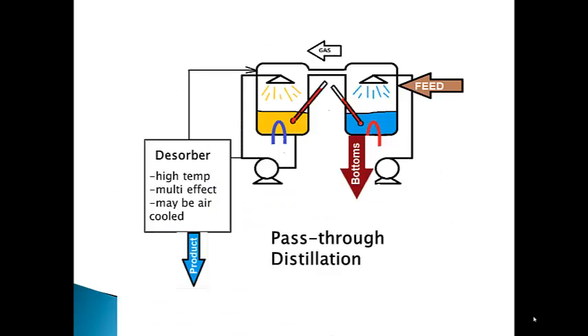We have learned that the desorber may operate with a very high temperature first effect, that it can have up to 4 effects, and that it may be air-cooled. But to operate at all, it needs a vacuum pump. An absorption chiller does not have one because it is a closed system. But pass-through distillation is an open system. Dissolved gases in the feed must be continually removed in order to maintain the desired operating pressure.